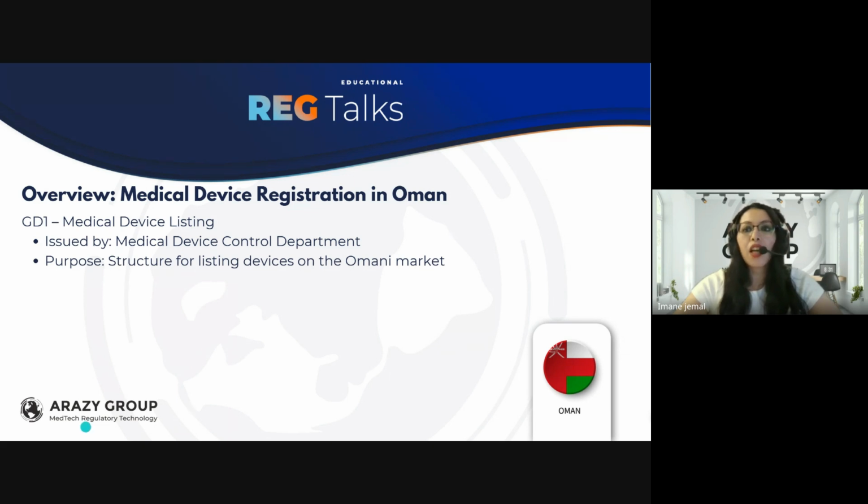As I just mentioned, listing was the initial and only process used to bring medical devices to the market. It was designed to keep a record of what devices are available, involving only basic information like the manufacturer name, contact details, device code, intended use, and so on. It did not require any technical documentation, clinical study, or labeling review. And now, with the implementation of the full medical device registration, listing is no longer sufficient. It is applicable, but no longer sufficient on its own.